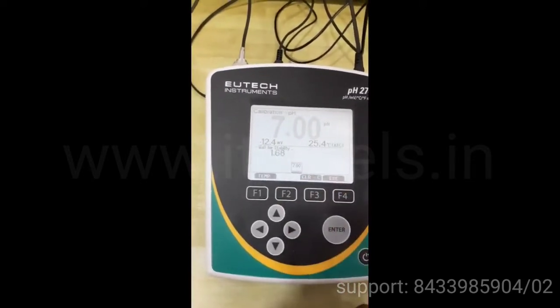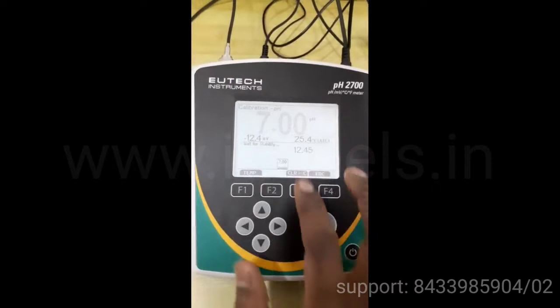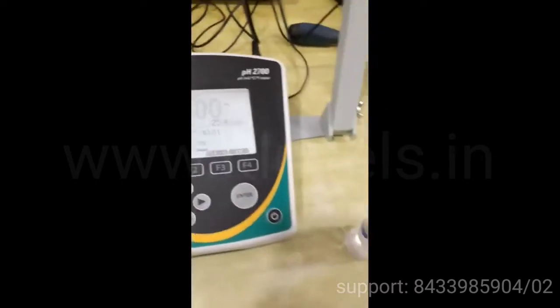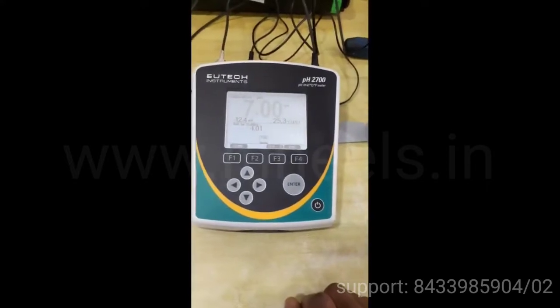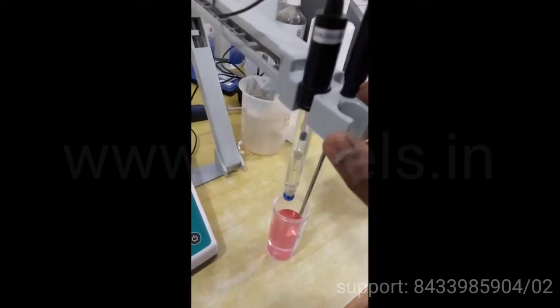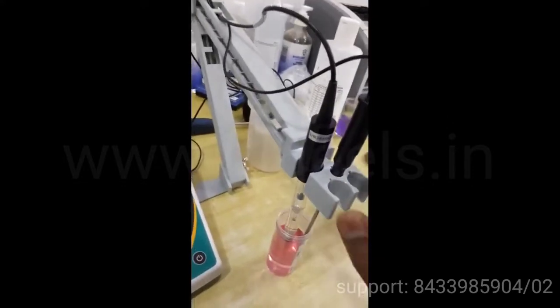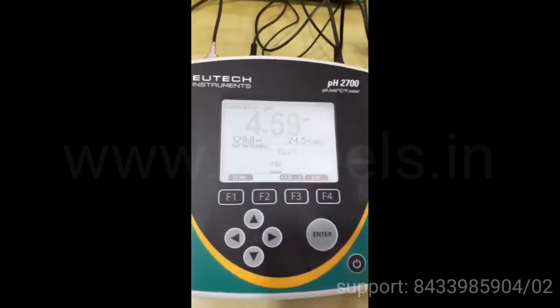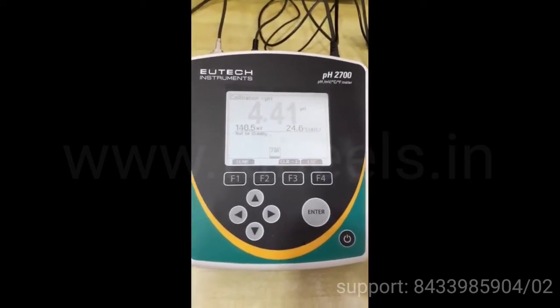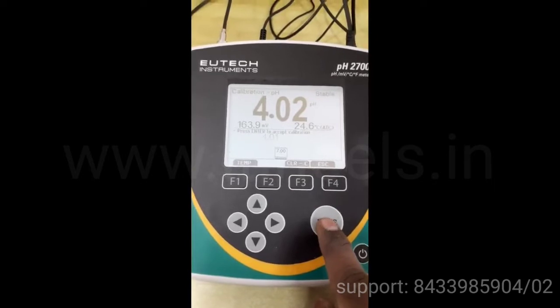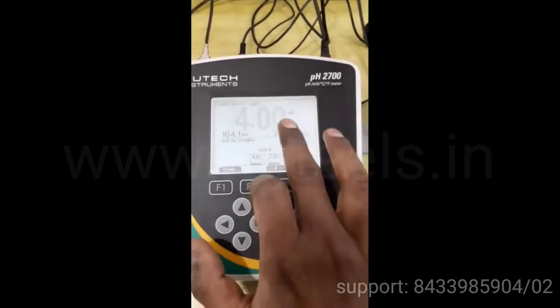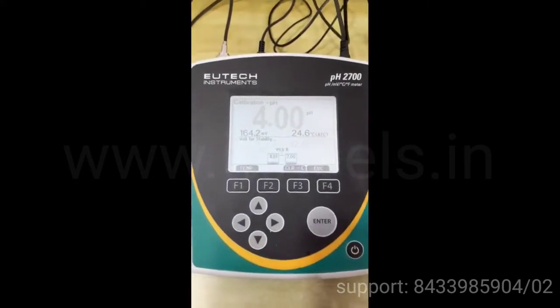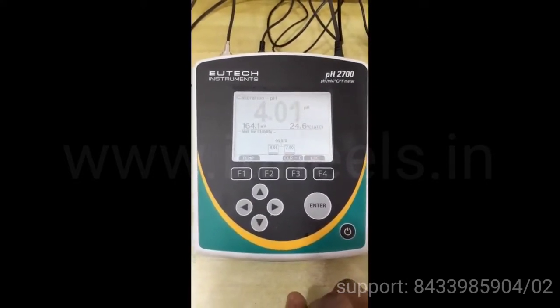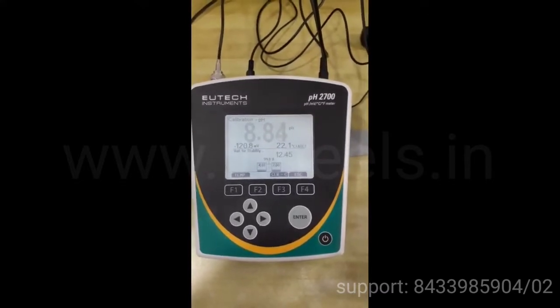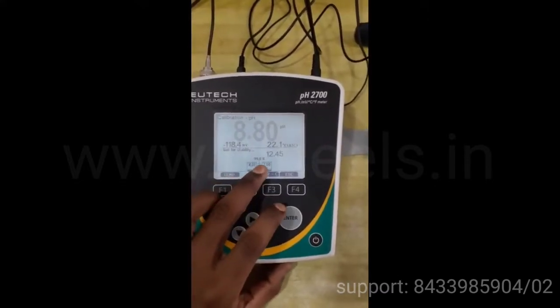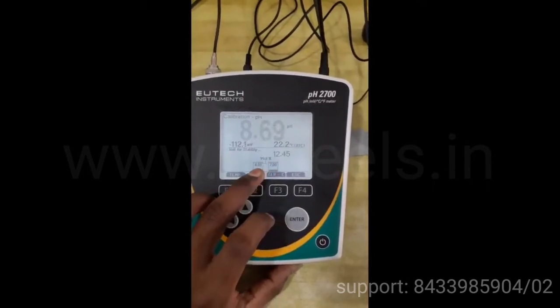Then you have to press enter. Then it will ask for other buffer point samples. You can dip in any of these buffer samples now after cleaning the electrode and ATC probe as shown before. Now after cleaning the electrode, dip it in another buffer standard. Now we are dipping in 4 and waiting for stable readings. After getting a stable reading, press enter to accept the calibration. Then you can dip it in any of these buffer points after cleaning the electrode. You can calibrate the meter for up to 5 points. Now we are calibrated for 2 points. It is also displaying the slope between 7 and 4.